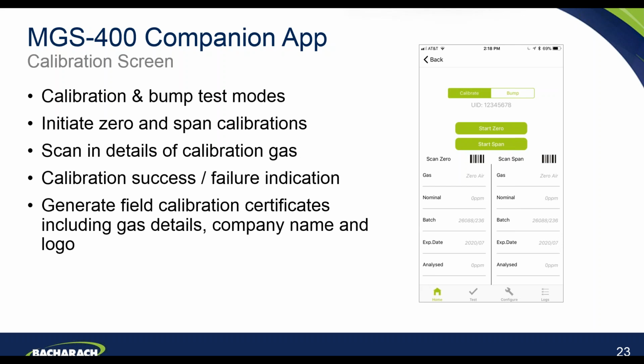On the calibration screen here, you can see we have the capability to perform a full calibration of the instrument or a simple bump test. You can see the green buttons there say start 0 or start span, so you can do a 0 calibration and a full span calibration. One of the unique features of the app is that, just below those green buttons, there is a scan 0 and scan span with a barcode next to them. You can use your smart device to scan the QR code on the cylinder of calibration gas, and then all of the calibration gas details will be populated in the fields just below. It will show you the gas, the batch number, the expiry date, to give that information from a traceability perspective for your calibrations. So you can scan that detail in.